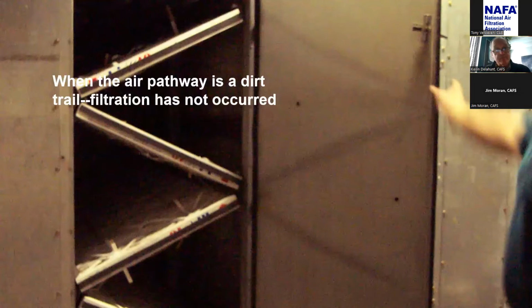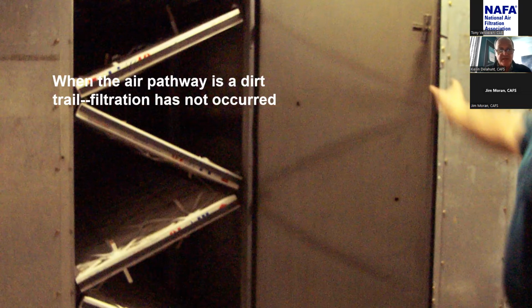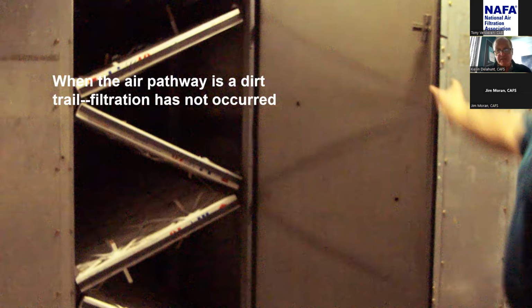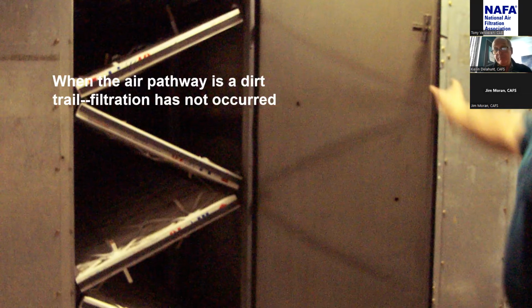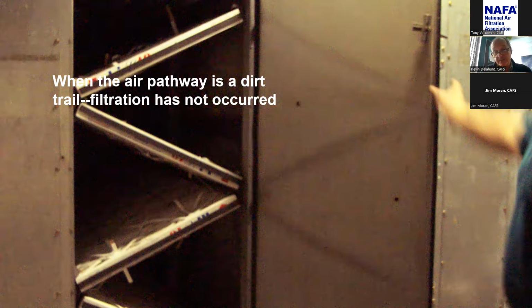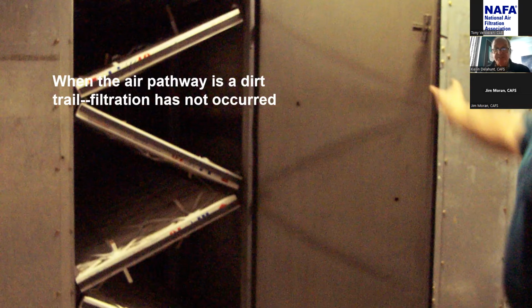Okay. Very evident here. You can see the air path going next to the door, bypassing the filter and actually leaving a dirt trail where the air is speeding by the filter, completely bypassing the filter system. And in these cases, we need probably more and better gasketing and a tighter seal, more pressure on the filters to hold them in place. And at the end of the day, probably even better hardware from the equipment manufacturer to make sure that the filters actually provide 100% seal. Again, all the air going through the filter.